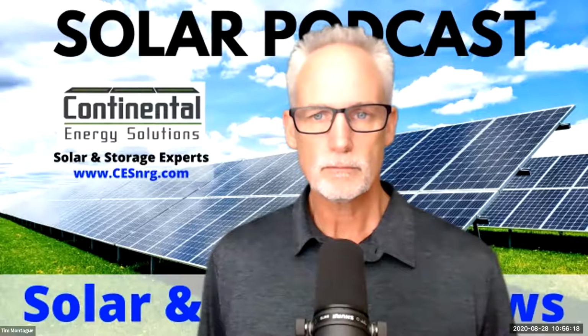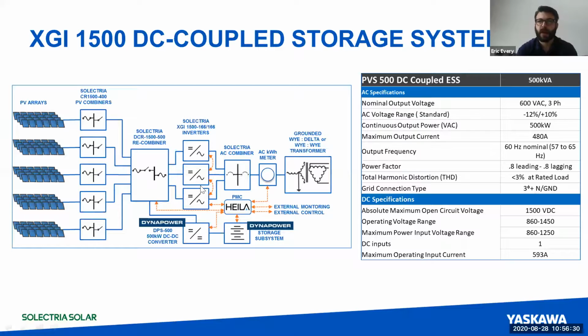One of the ways that we combat that a little bit in our energy storage solution is that we run 3 inverters in parallel. And I'll show you what that looks like here. Okay. If I can share my screen. So we have our 166 kilowatt inverter, and what we do is we take 3 of them and put them together on the same DC bus. There we have the Solectria 166, our flagship PV product. We make 2 small modifications, one to the control board and one to the DC disconnect, to make it our energy storage capable unit. We put 3 of those in parallel.